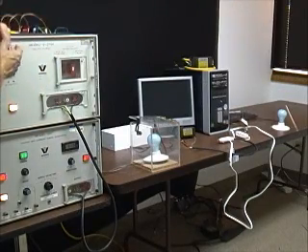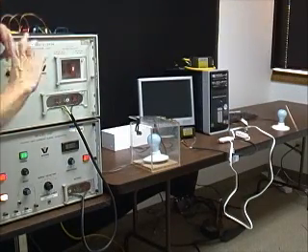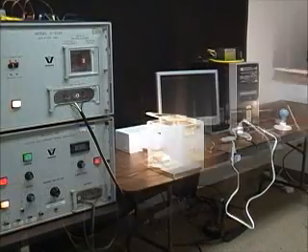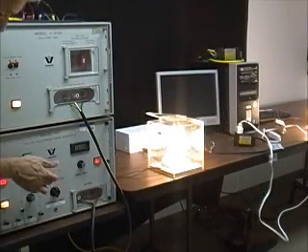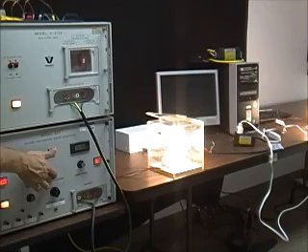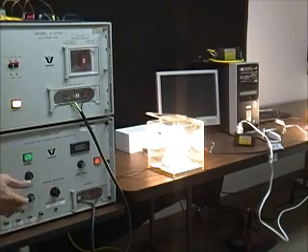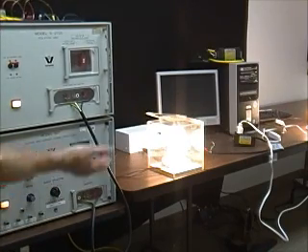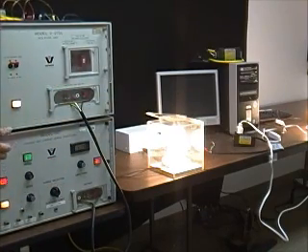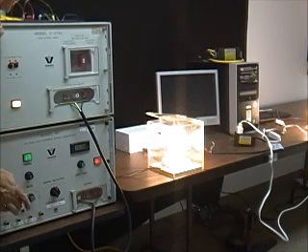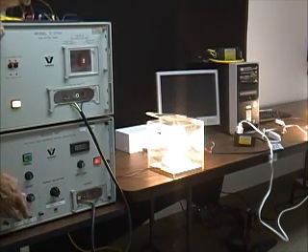Now we'll reintroduce two new light bulbs, the suppressor, and change to the combination wave. Okay, we're back now. We have changed the surge generator to the combination wave, six KV, three K-A. Reintroduce the SineTamer into the circuit. Now let's see what happens as we begin to release the surges.